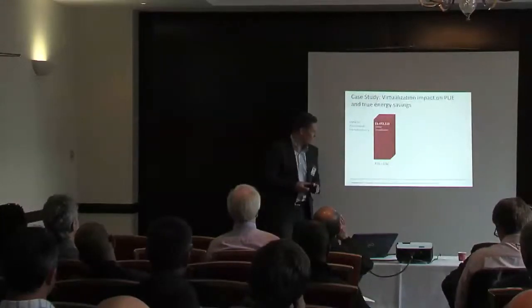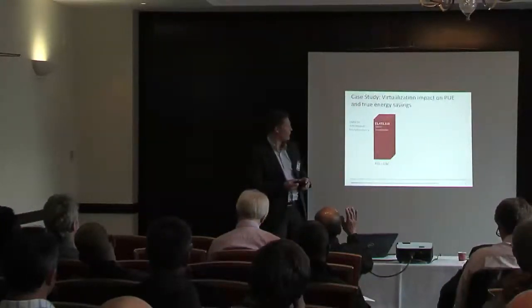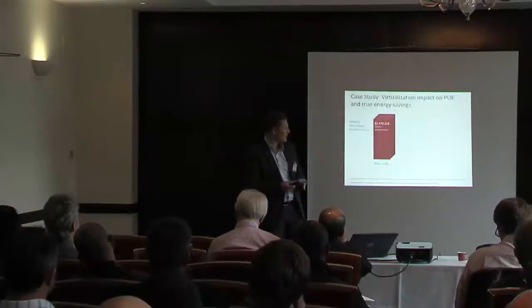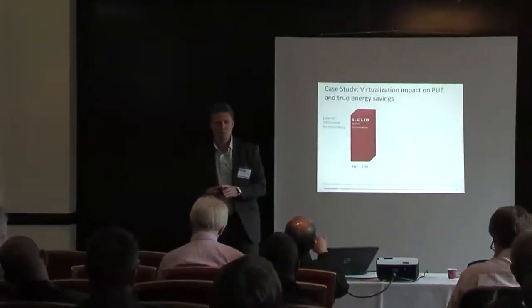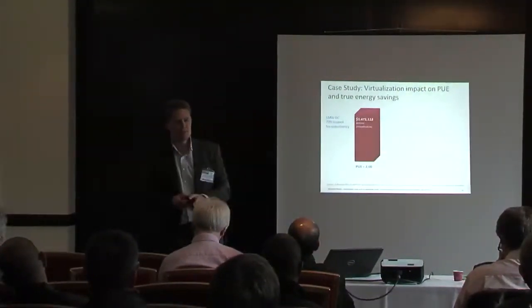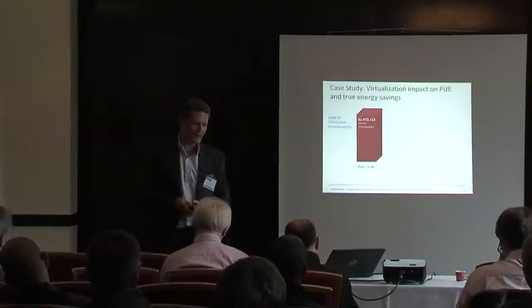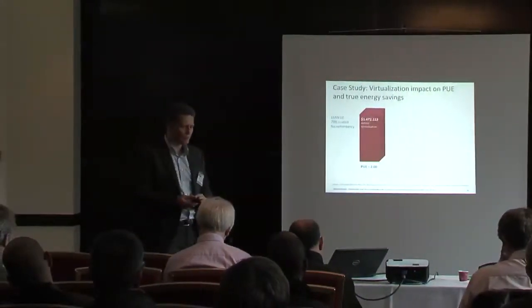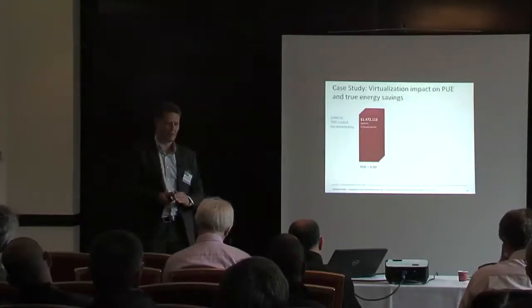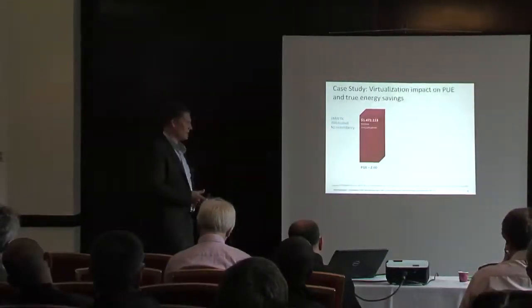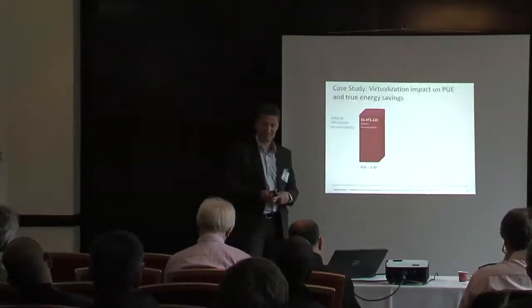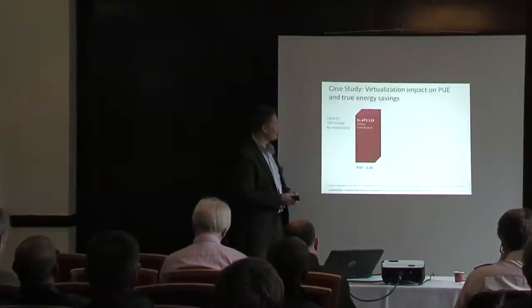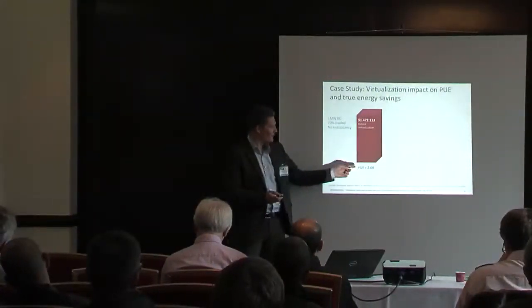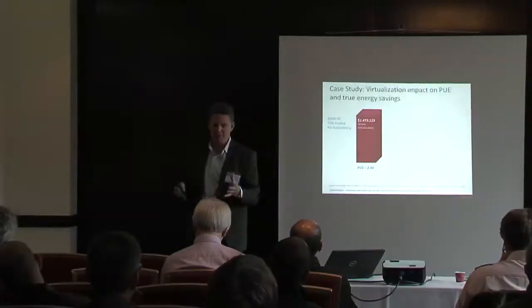This is a North American data center running around 1 megawatt, 70% loaded, no redundancy, with a PUE around 2.0. Power usage effectiveness is basically a metric indicating how much of the total power ends up in the IT equipment, and thereby how much is lost everywhere else. So 1 is the ideal, and getting to 1 is very difficult, actually impossible. Okay, so now we have a data center, that's our foundation.